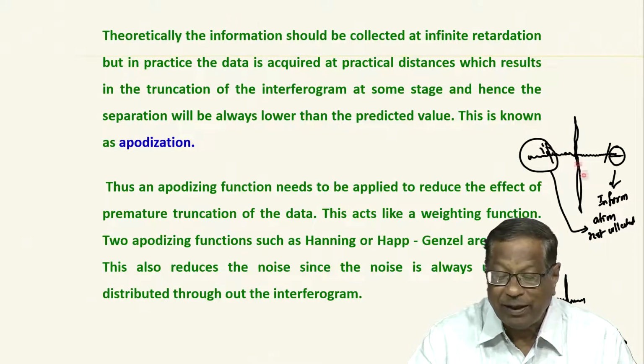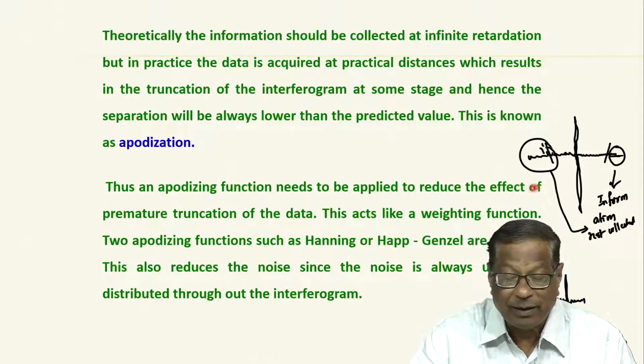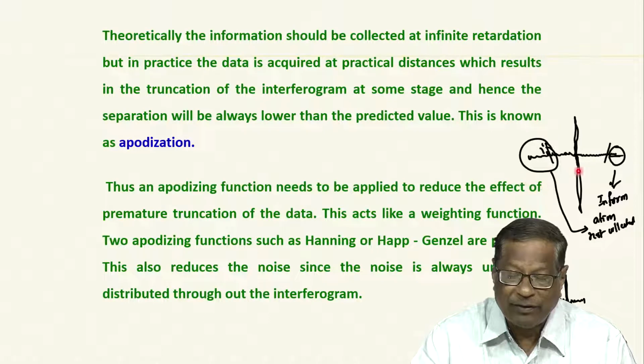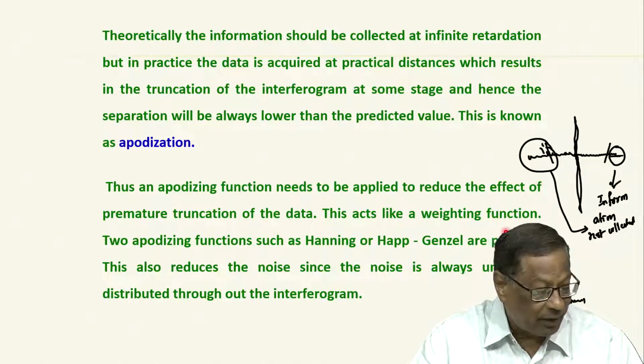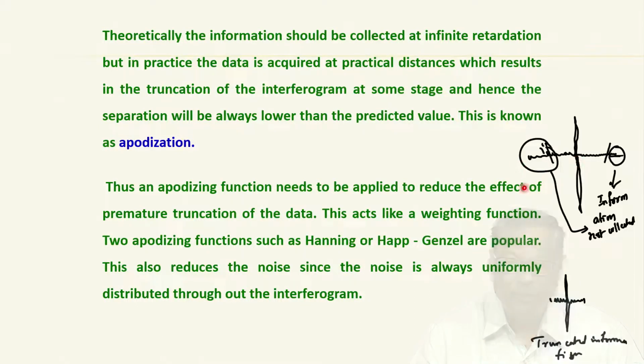That I had shown you here. This is known as apodization. This is also done mathematically with a computer program incorporated in the instrument itself, the microprocessor, and two general apodizing functions are there, that is basically a weighting function or correction factor we have to apply.